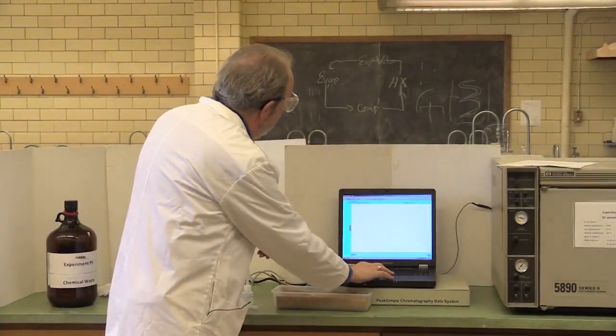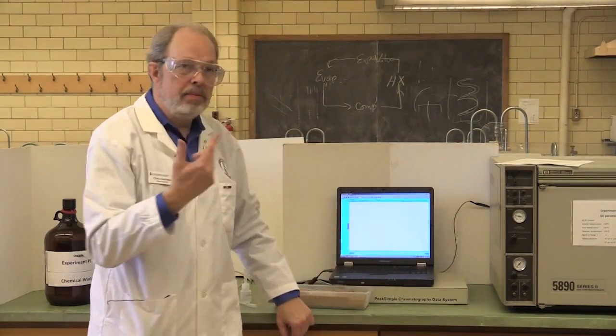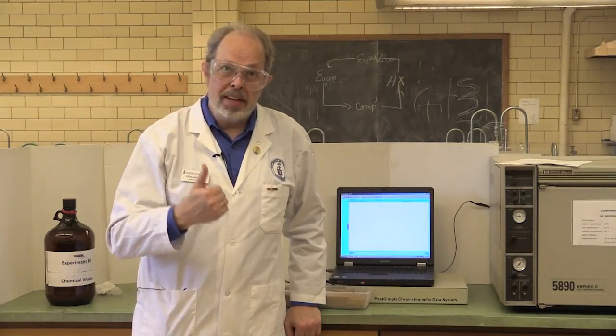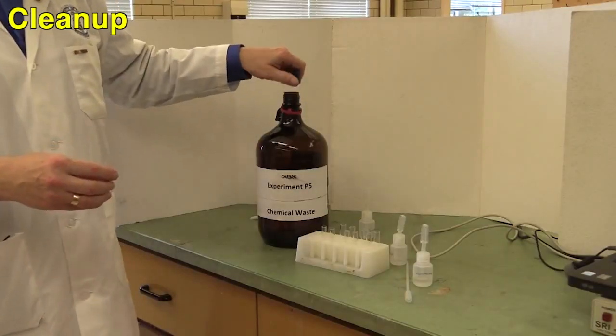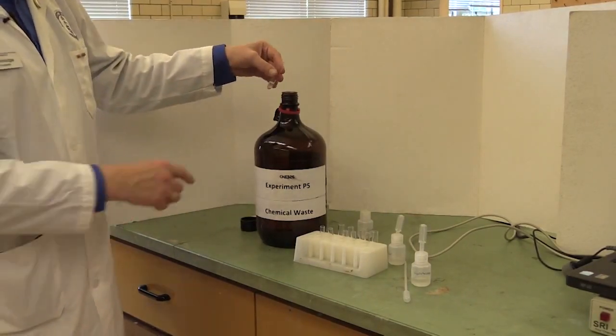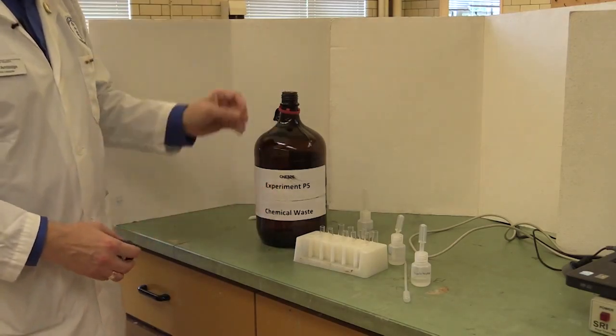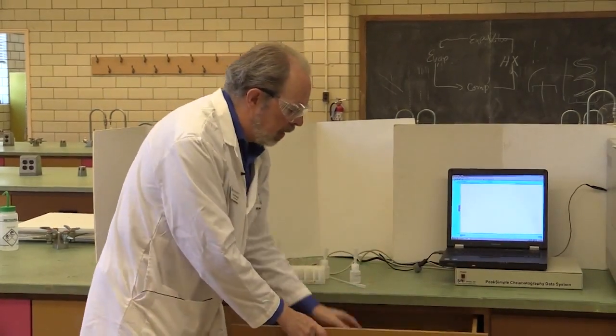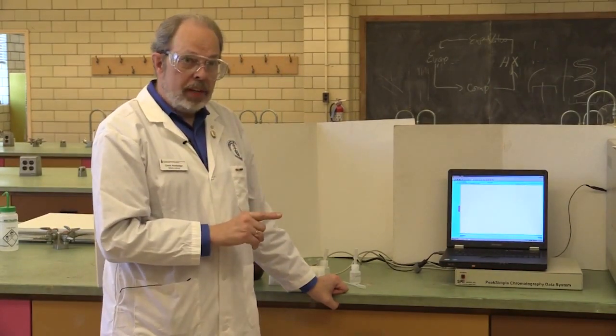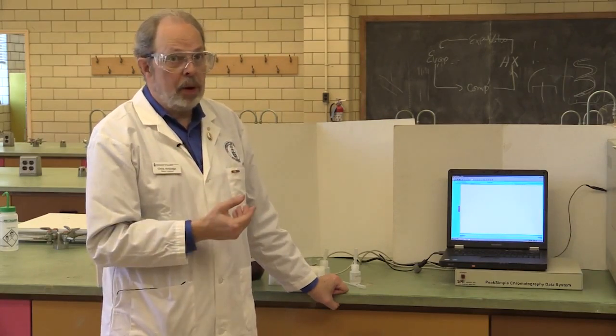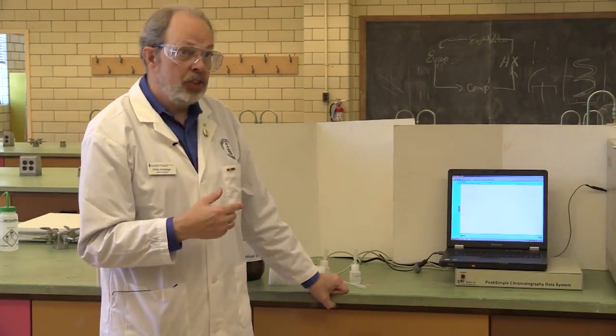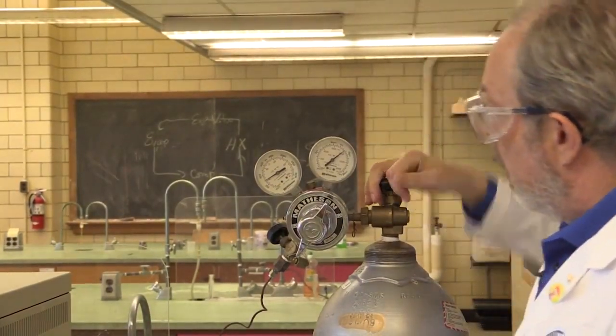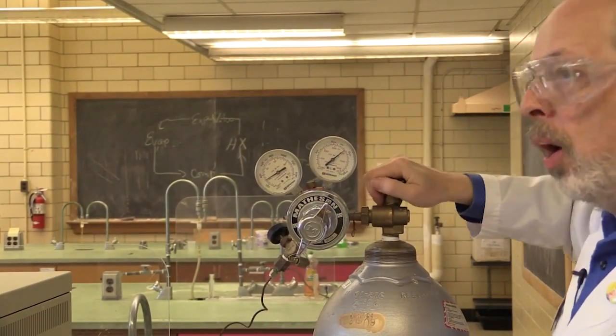Once you've done one run, when you're doing the next one, you click in the top left-hand side for new, and that's ready to start another injection. Once you've finished doing all of your injections, it's time to clean up. For this experiment, it's really quite easy. We've got a waste bottle labeled for experiment P5. You dump all of your solutions into there, and stopper it, and everything goes back into the locker, and the syringe goes down into the drawer. You don't need to wash any of these, they're pure solvent, so when they dry by the next experimental time, they will be clean. The other thing you have to do, of course, is turn the computer off, and likewise the GC. So you shut off the gas flow, turn that all the way clockwise, righty tighty, and turn the power off. Turn off the computer, give it back to your TA, and you are done. And that is how you perform experiment P5 ternary system in two phases.